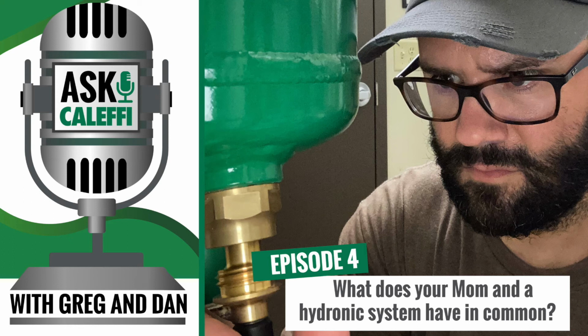Certainly is. So what about installing these things? You have any tips for the guys out there? Yeah, I always like to put them on the return side of the system. If I can put them in right before the boiler, then I know I'm protecting the boiler heat exchanger. Again, you want to make sure that you're going to be piped in line, so that you get that good velocity drop as that water passes through it. Absolutely, and that's protecting the boiler, catching the majority of the debris on the first couple passes and keeping it out of those smaller passageways and some of these very restrictive heat exchangers that are out there.